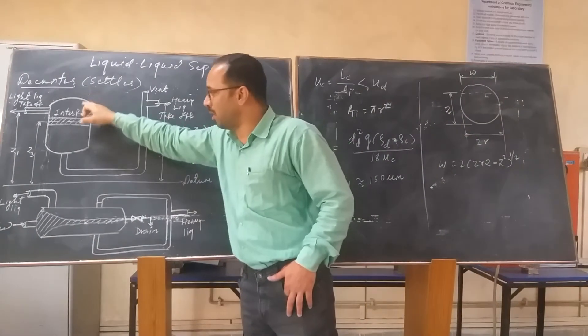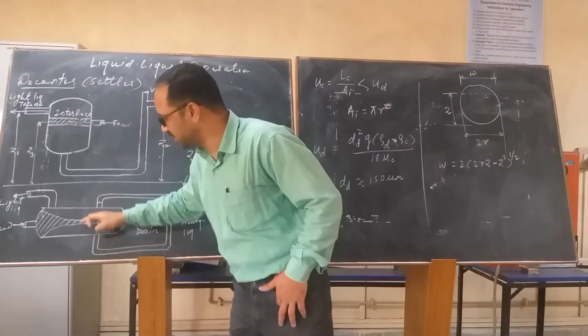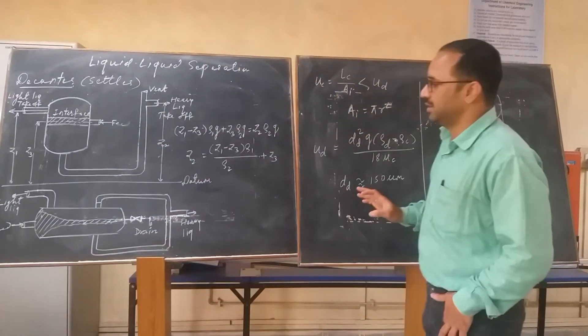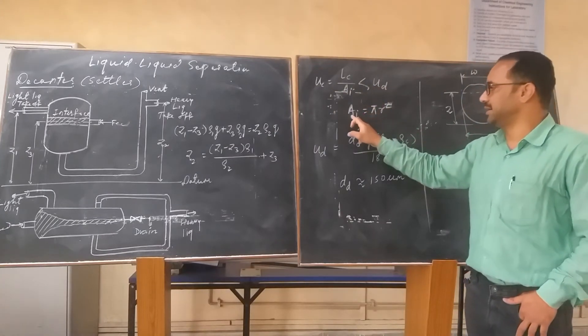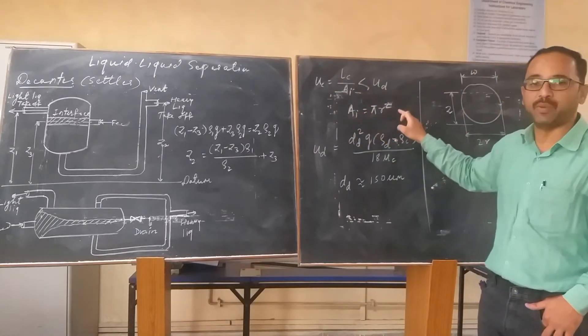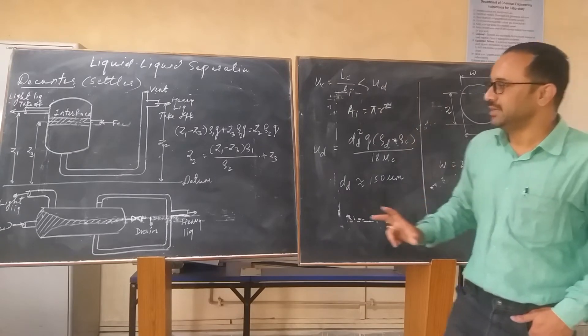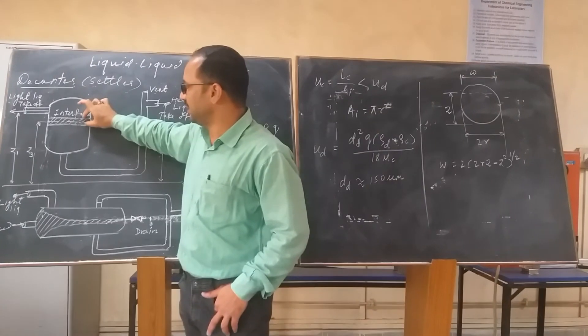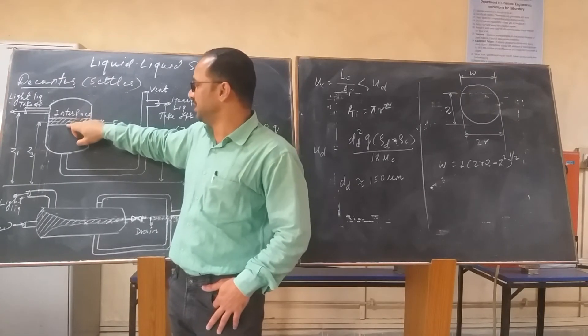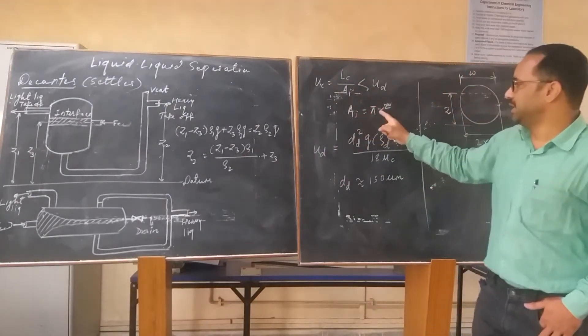The area of the interface is constant in the case of a vertical decanter, whereas it varies depending on the location of the interface in a horizontal decanter. For the vertical decanter, the area of the interface is equal to πr², where r is the radius of the decanter. Generally, 10% of the height is provided for the interface to give sufficient time — typically 5 to 10 minutes — for droplets of the dispersed phase to settle.